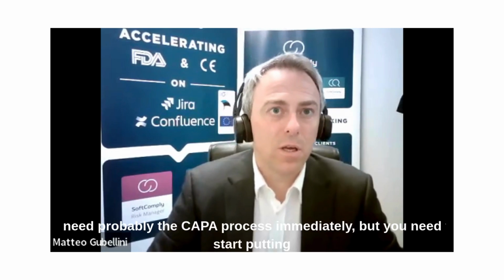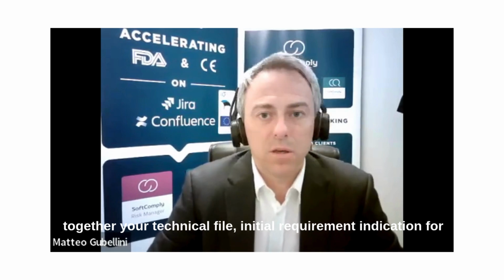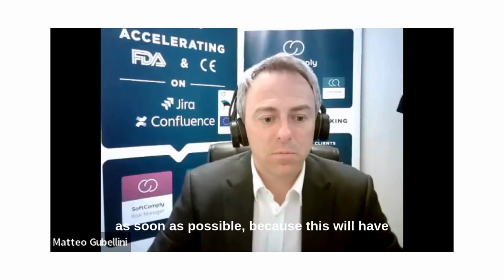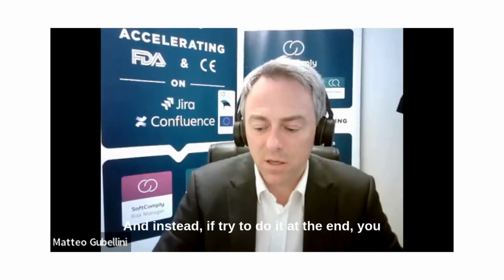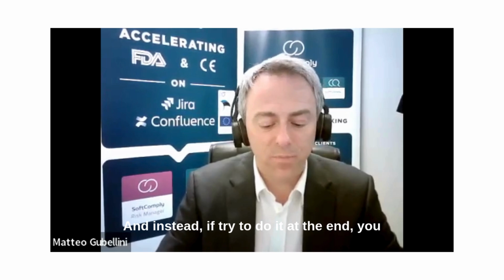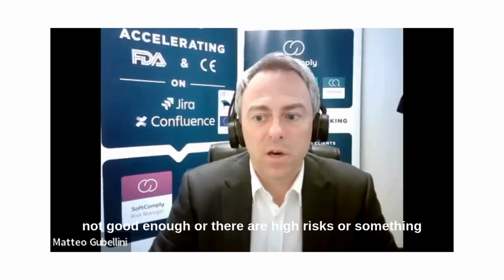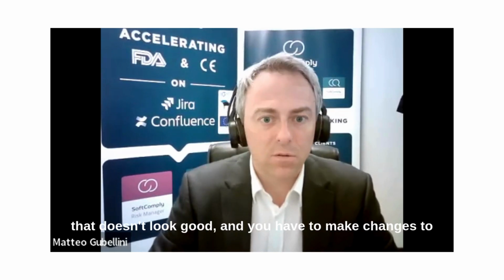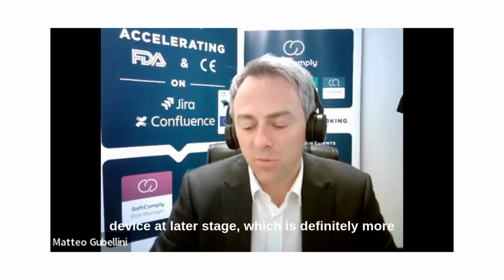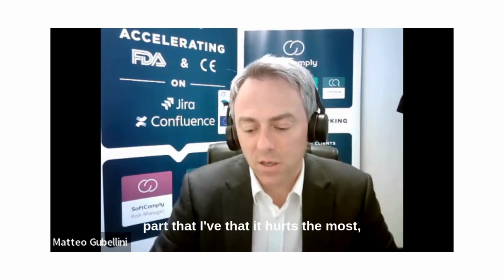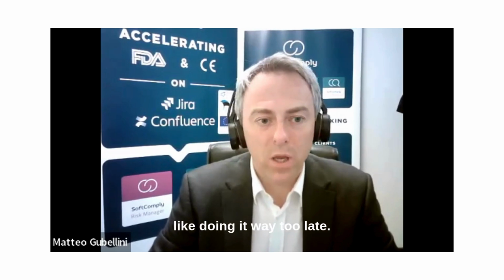I mean, you're probably not going to need the CAPA process immediately, but you need to start putting together your technical file, your initial requirements, and indications for use as soon as possible, because this will have a ripple effect on the design of the device. Instead, if you try to do it at the end, you do all your risk analysis, and then you realize that things are not good enough, or there are high risks, or something that doesn't look good, and you have to make changes to the device at a later stage, which is definitely more painful. This is the part that I've seen hurts the most, doing it way too late.